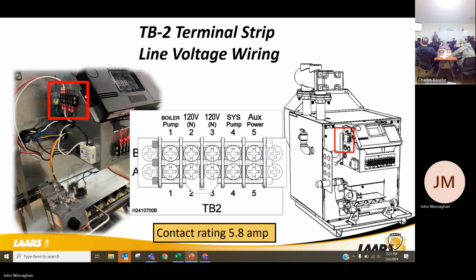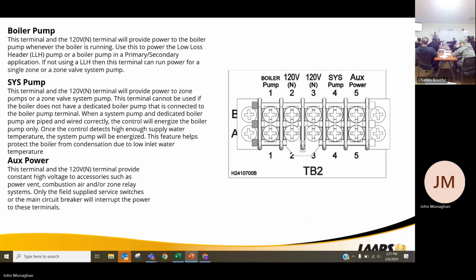Good. Your line voltage, you would have your 120 volts in, system pump, your auxiliary power. Contact rating is going to be 5.8 amps. Boiler pumps would get wired for 1 and 2. System pump would be 3 and 4. Auxiliary power would be like your fan or your fan kick.